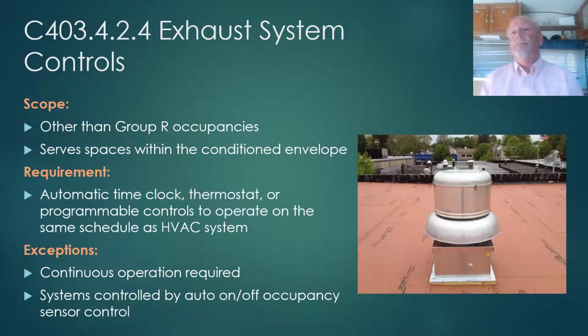Exhaust systems. Exhaust systems have been left out of the control requirements, interestingly enough. When you look at automated controls, it focuses on heating and cooling systems but failed to represent exhaust systems. And so we now have a specific independent control requirement for exhaust systems. So in other than group R occupancies, exhaust systems that serve conditioned spaces shall have an automatic time clock control, a thermostat or programmable control to operate on the same schedule as the HVAC system. It makes no sense to operate the exhaust systems when the spaces are unoccupied.